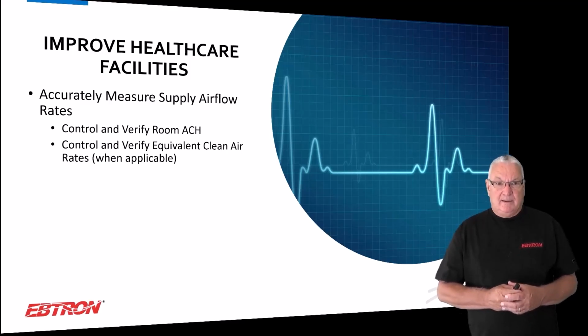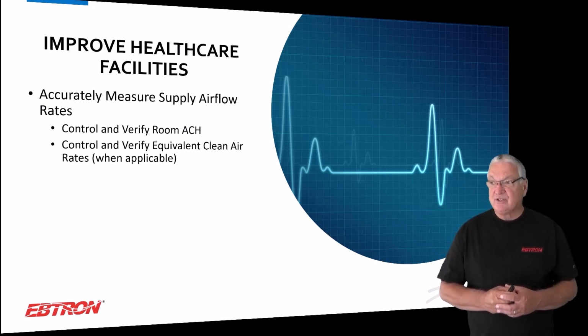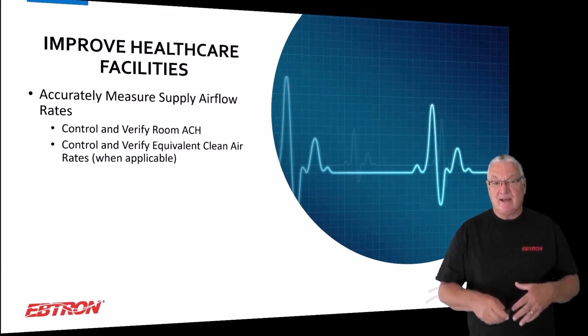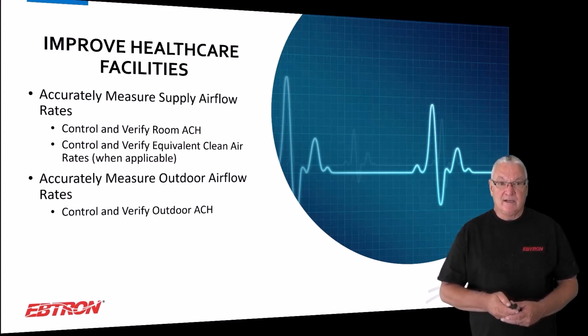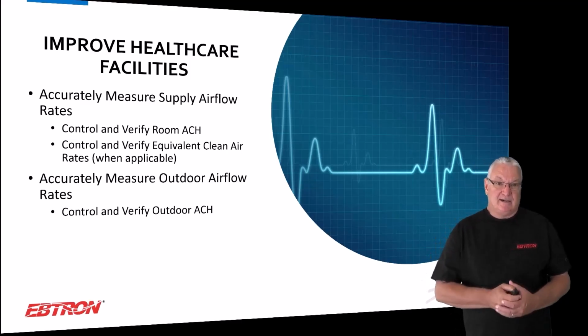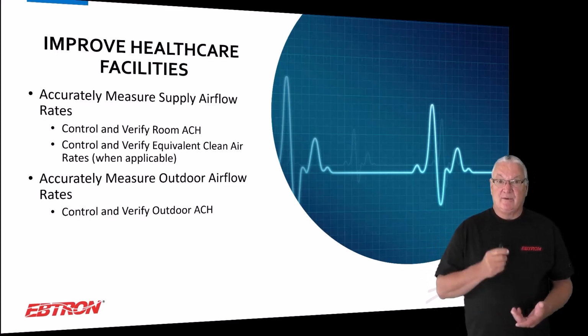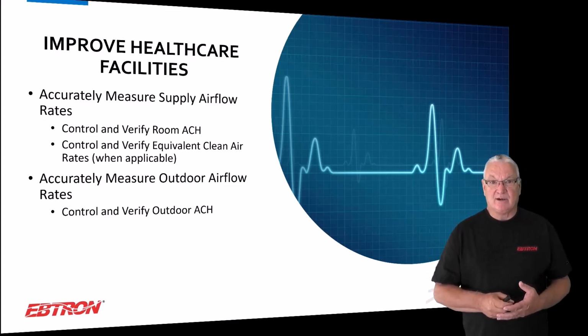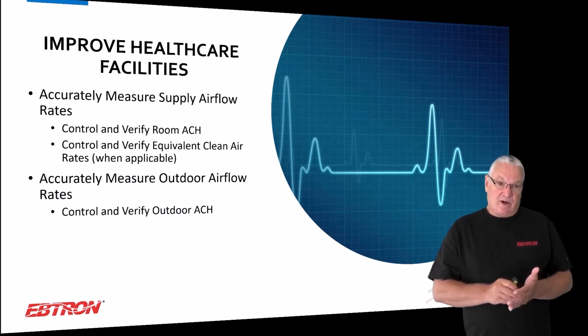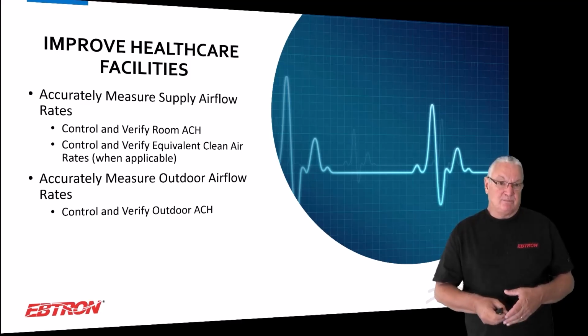And then there may be some of you that use equivalent clean air to reduce outdoor airflow rates. So if you're doing that, I think it's even more important to be able to show that you've actually provided the supply airflow rates that you need as the equivalent clean air flow rate. Getting into outdoor air, we need to accurately measure outdoor airflow rates so that we can control and verify outdoor air changes per hour. Outdoor air is an extremely expensive thing, but it's very important too. So we want to provide what we need. We don't want to provide too much. We don't want to provide too little.